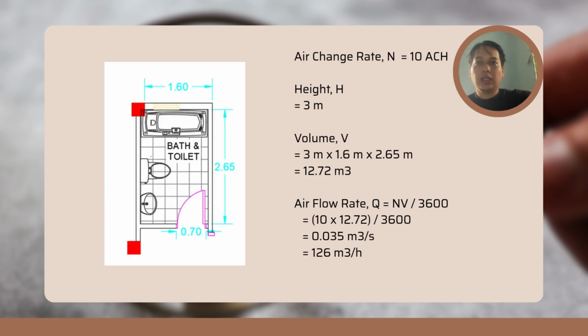So the last area was toilet or bath. The air change rate was 10 ACH, the height was 3 meter, the volume was 12.72 meter cube, and the airflow rate was 126 meter cube per hour.